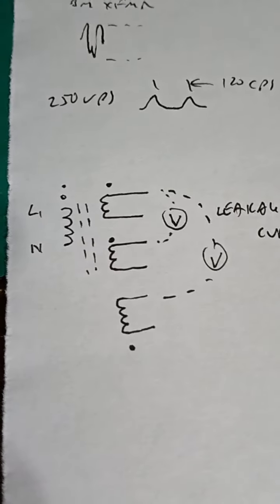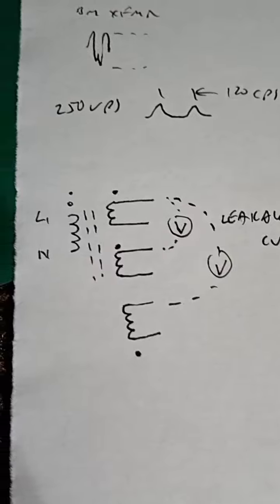Those phasing dots indicate arrangement of the windings with regard to each other and perhaps with the core. And what's important is to understand that there are leakage paths, literally for magnetic flux and current, from the primary to the secondaries through the core and also among the secondaries. And it may be helpful, especially in applications that need to be very clean, to phase these leads.